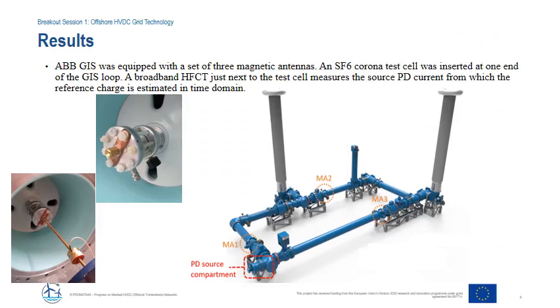Further experiments were carried out, this time using HVDC GIS in Arnhem. A set of 3 magnetic antennas were installed in different locations, together with an SF6 corona test cell at one end of the GIS loop. A broadband HFCT just next to the test cell measures the source PD current from which the reference charge is estimated. In this setup, there are many more parts and components between the PD source and the antennas. This allowed testing the influence of the attenuation and distortion of the signal in the charge estimation.